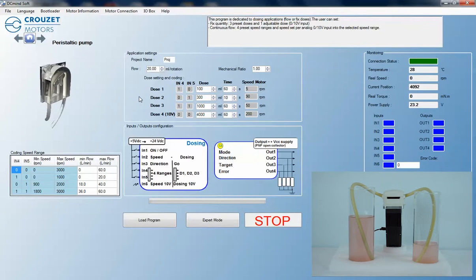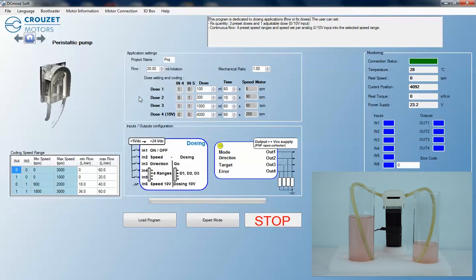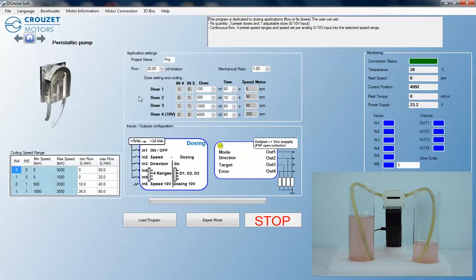We use the dosing feature in the application settings box with the ability to determine three individual doses by inputs and outputs, and one 0-10 volt DC proportional input. The software will automatically calculate the motor speed based on your mechanical ratio.